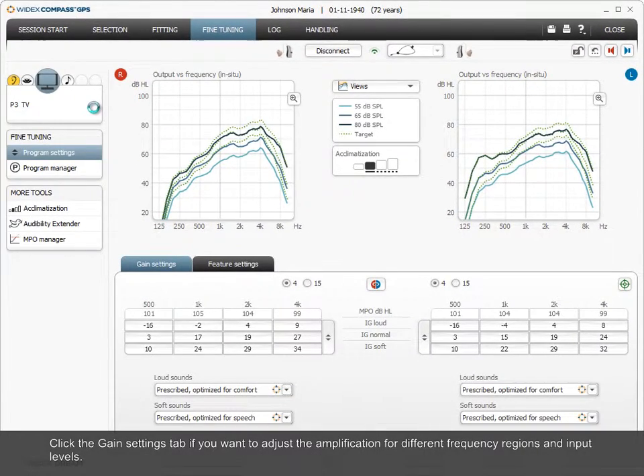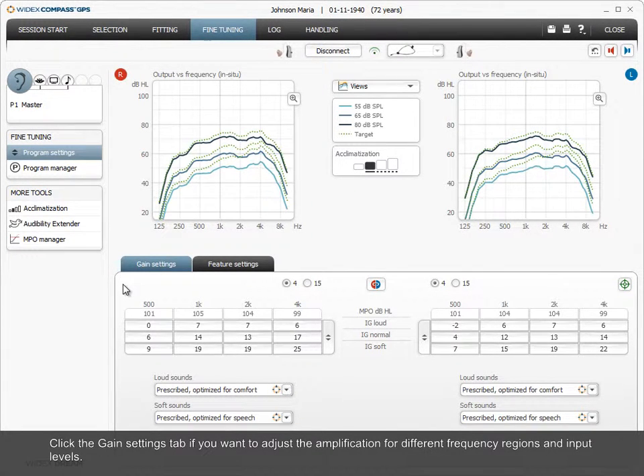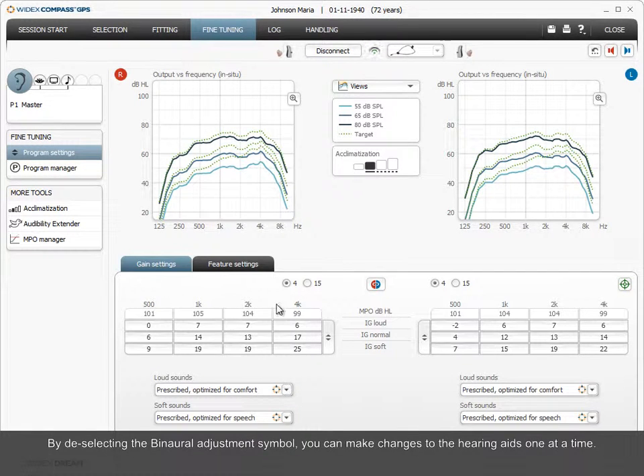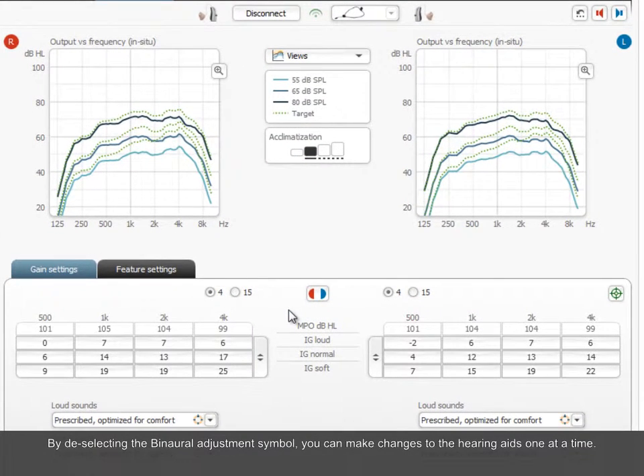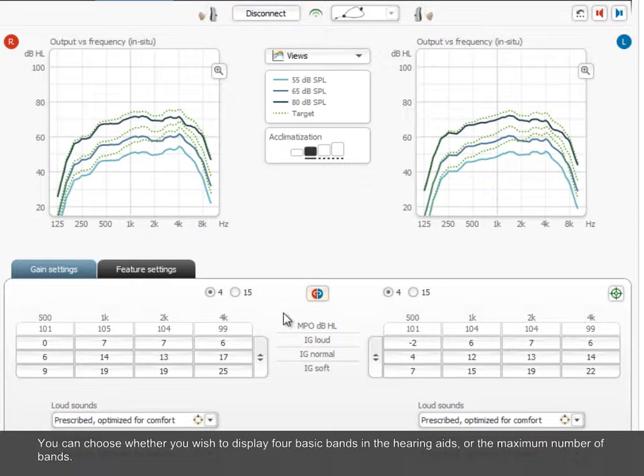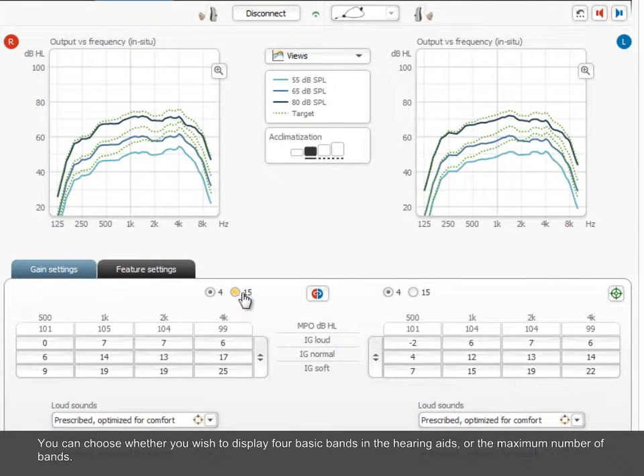Click the Gain Settings tab if you want to adjust the amplification for different frequency regions and input levels. By deselecting the binaural adjustment symbol, you can make changes to the hearing aids one at a time. You can choose whether you wish to display four basic bands in the hearing aids or the maximum number of bands.